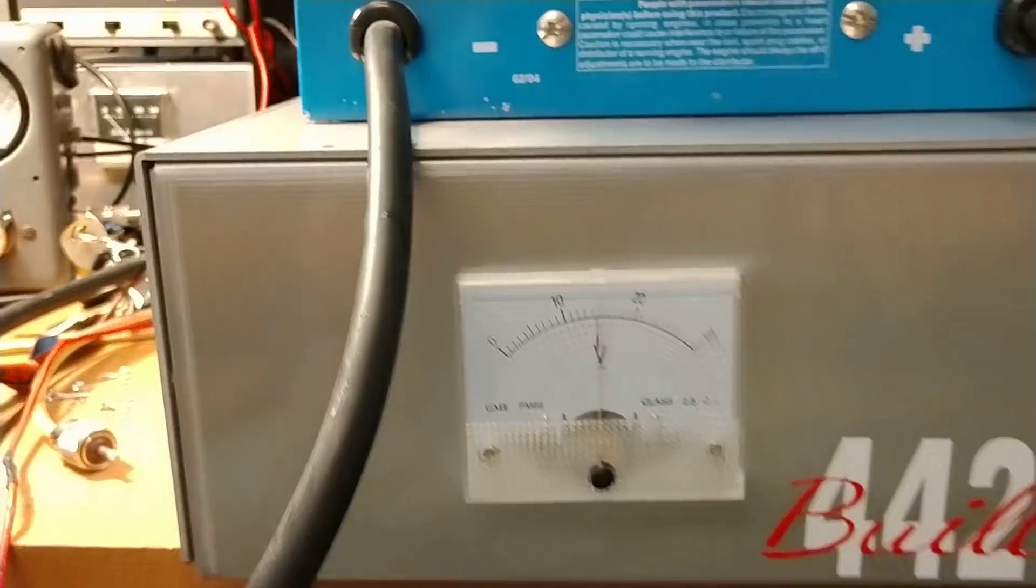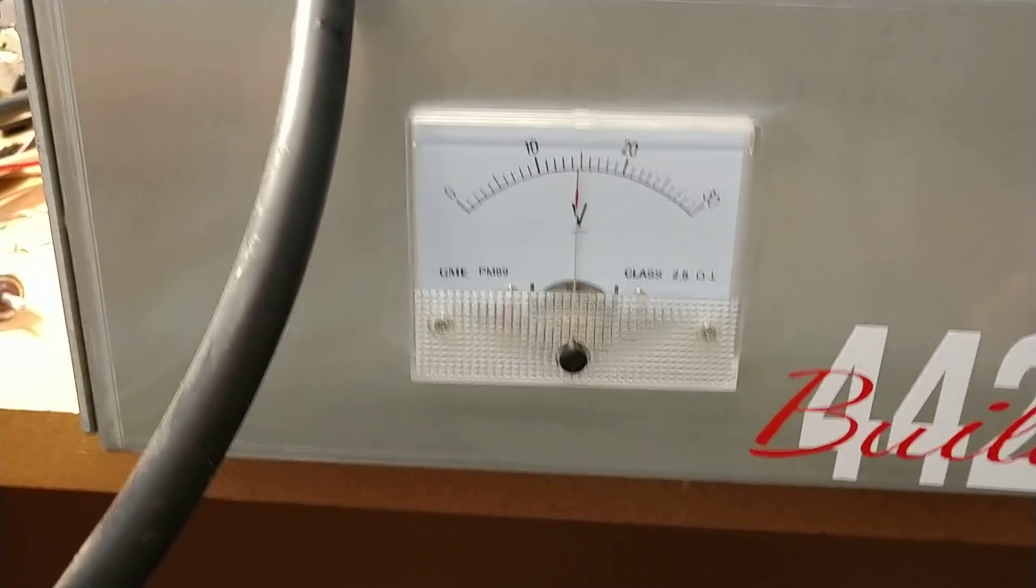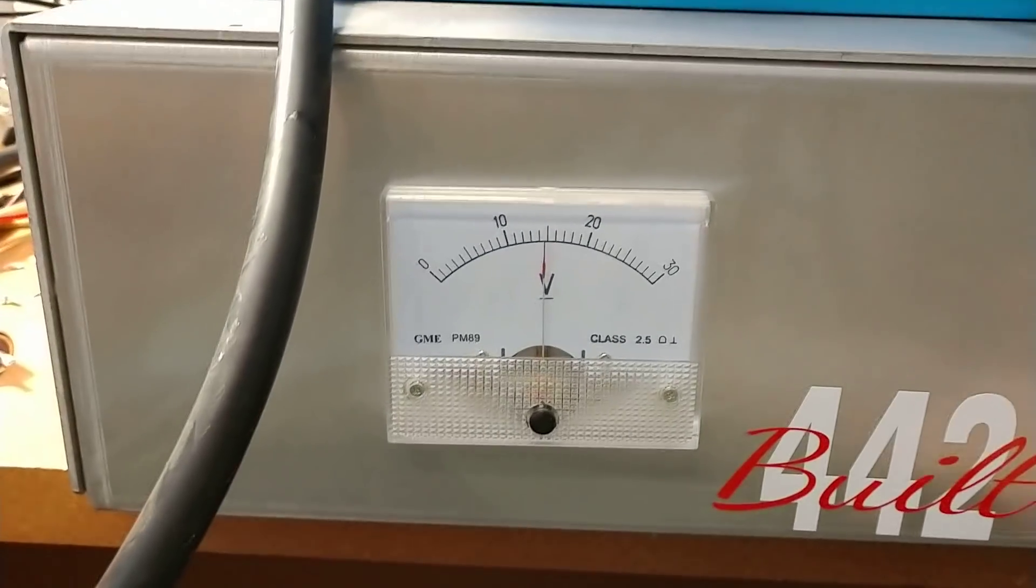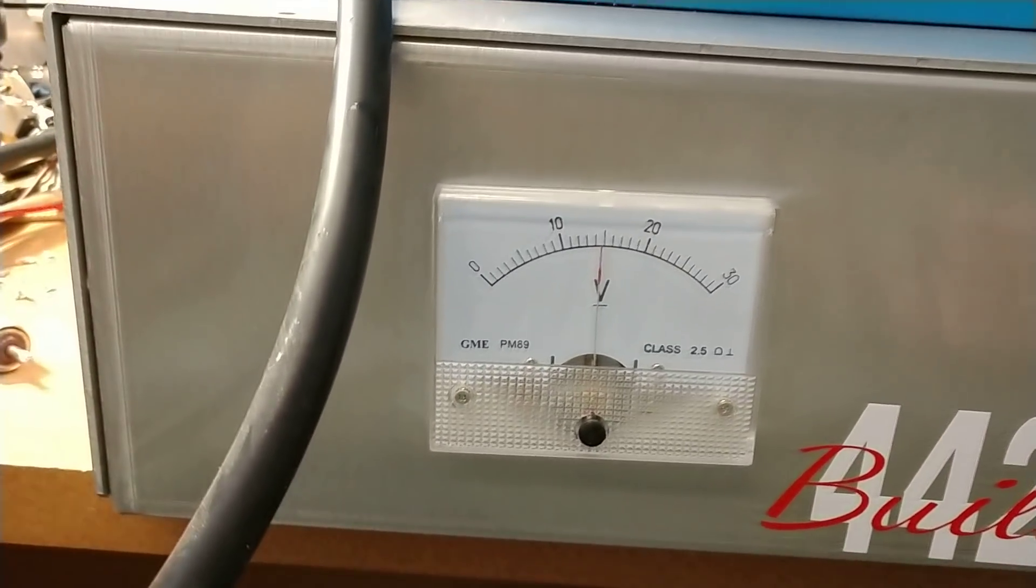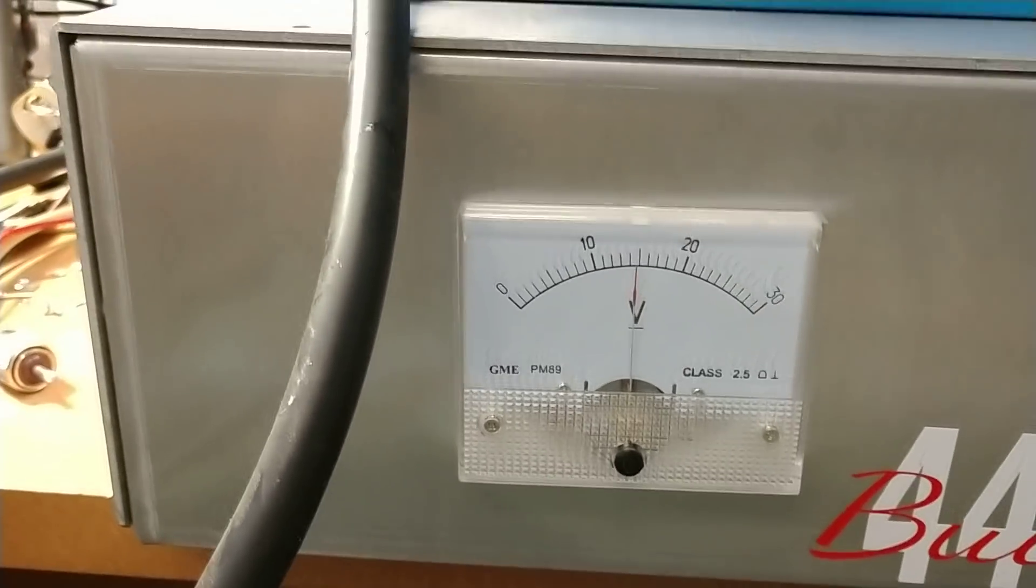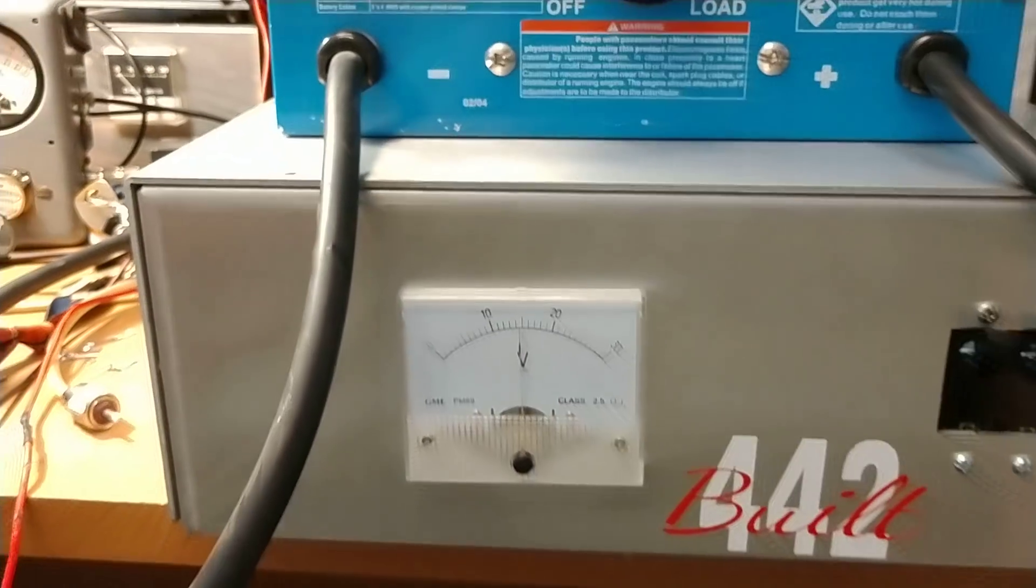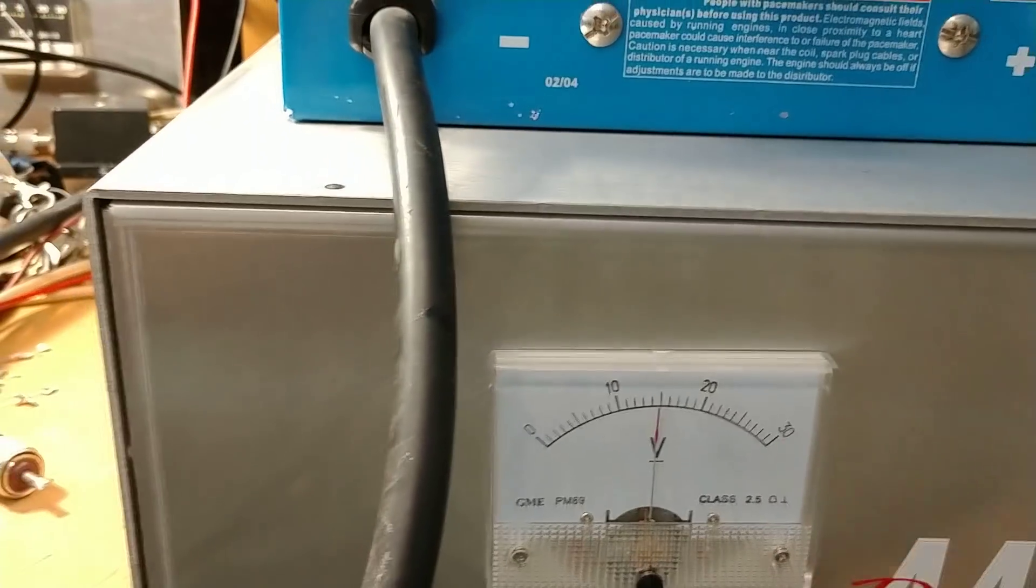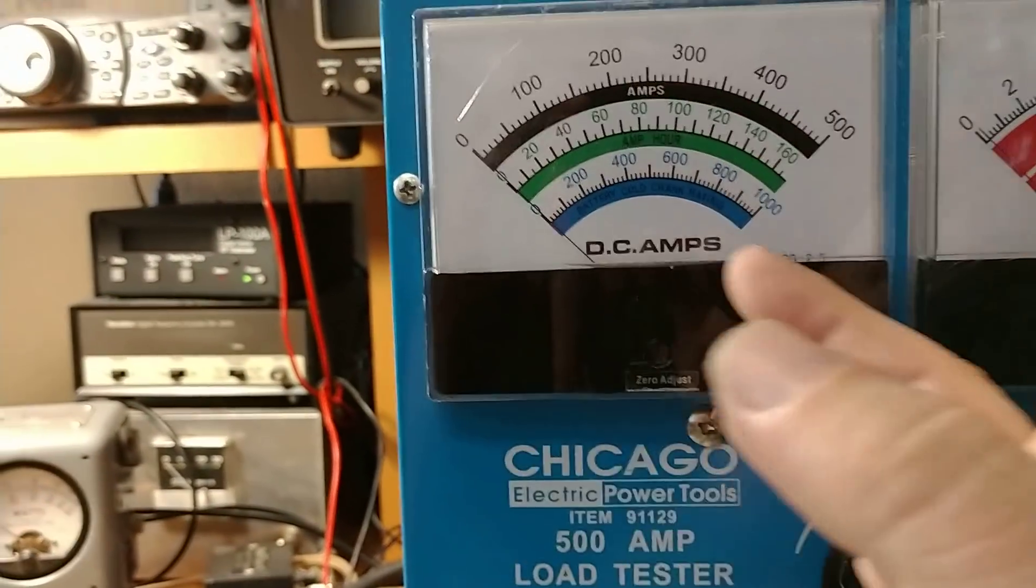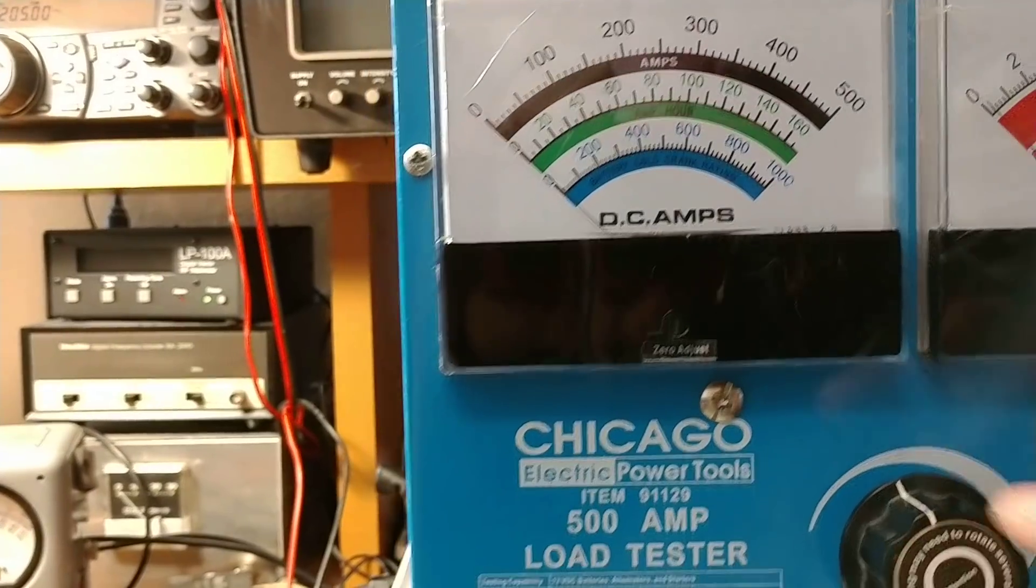Okay guys, when you're ordering a supply, you're going to order a bigger supply than what you're needing. If you need 500 amps, you're not going to order 500 amps. You would order like 750, 800 amps. You have to order bigger than what you're needing. And that's the case here. That's what Kirk did. He ordered bigger than what he needed, of course. So real world test is not going to be pulling this thing over 550, 600 amps in the corner.